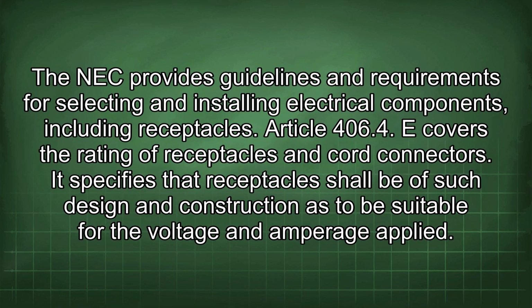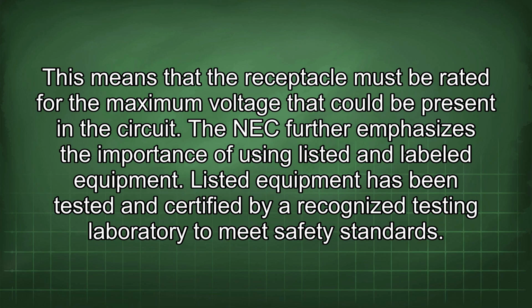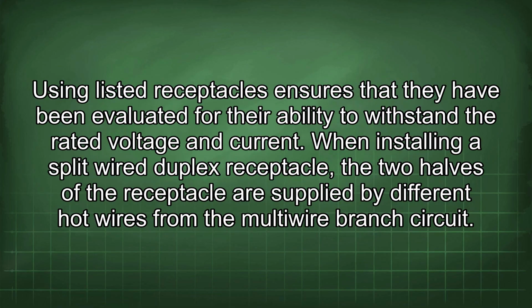The NEC provides guidelines and requirements for selecting and installing electrical components, including receptacles. Article 406.4 E covers the rating of receptacles and cord connectors. It specifies that receptacles shall be of such design and construction as to be suitable for the voltage and amperage applied. This means that the receptacle must be rated for the maximum voltage that could be present in the circuit. The NEC further emphasizes the importance of using listed and labeled equipment. Listed equipment has been tested and certified by a recognized testing laboratory to meet safety standards. Using listed receptacles ensures that they have been evaluated for their ability to withstand the rated voltage and current.